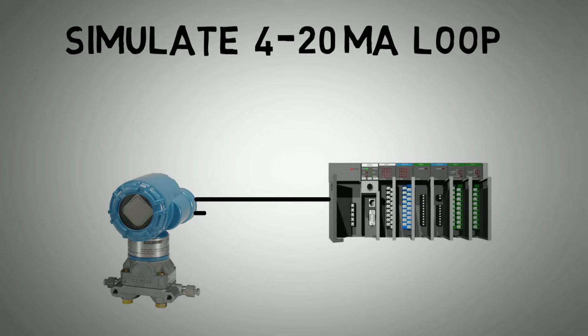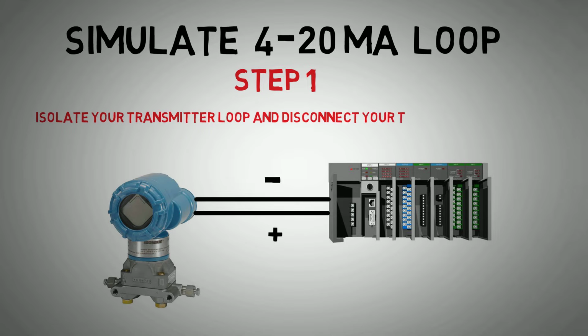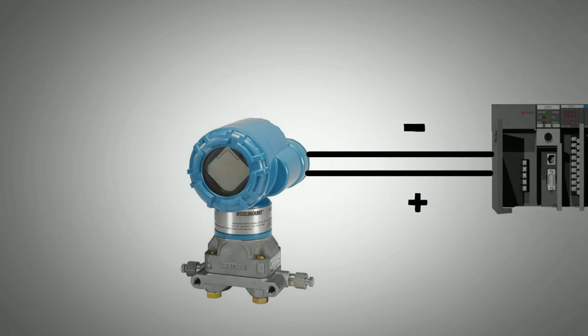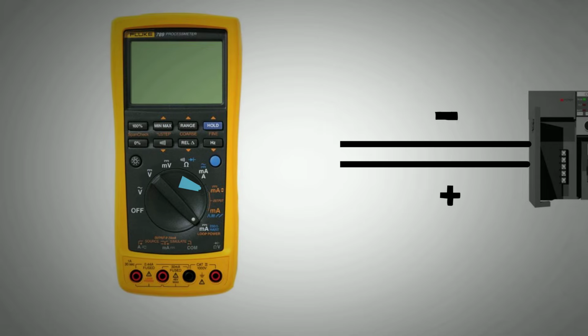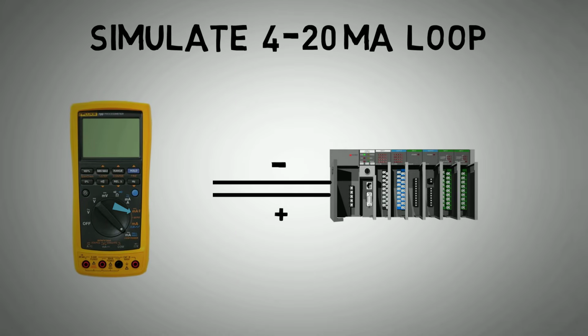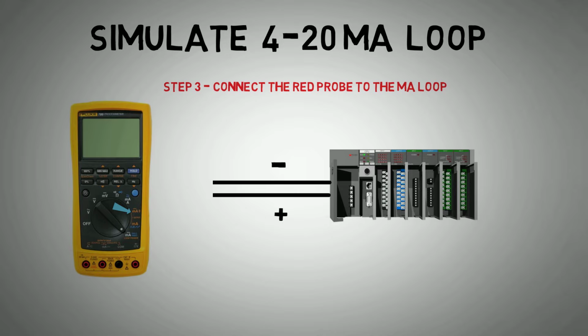For simulating a loop that is powered from the input card or barrier, follow these steps. Step 1. Isolate your transmitter loop and disconnect your transmitter at the head. Step 2. Put the transmitter into milliamp manual mode. Step 3. Connect the red probe to the milliamp loop power port on the meter and connect to the positive wire going back to your input card.